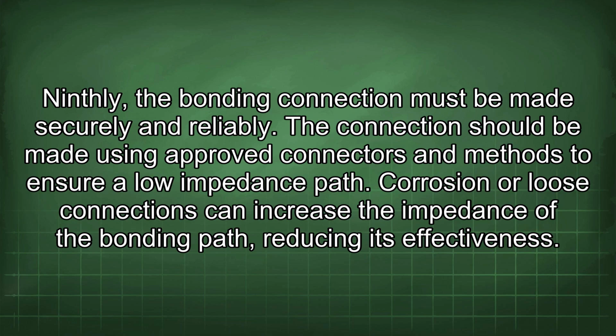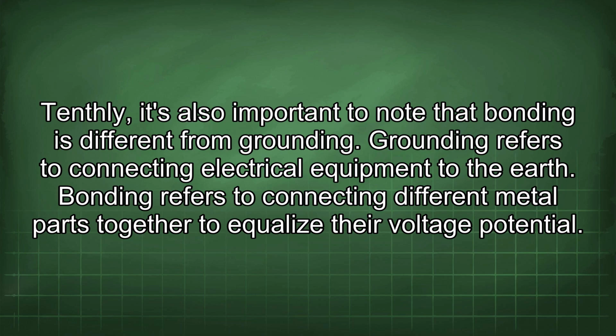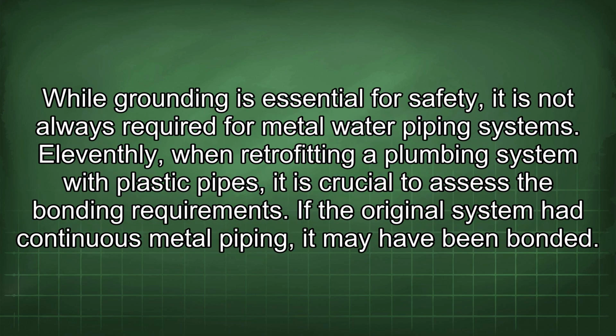Ninthly, the bonding connection must be made securely and reliably. The connection should be made using approved connectors and methods to ensure a low impedance path. Corrosion or loose connections can increase the impedance of the bonding path, reducing its effectiveness. Tenthly, it's also important to note that bonding is different from grounding. Grounding refers to connecting electrical equipment to the earth. Bonding refers to connecting different metal parts together to equalize their voltage potential. While grounding is essential for safety, it is not always required for metal water piping systems.